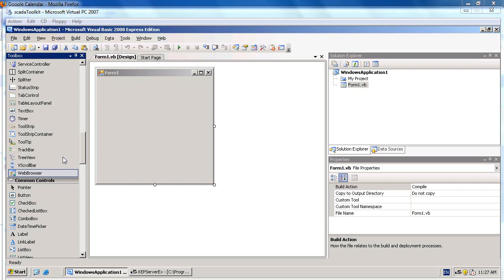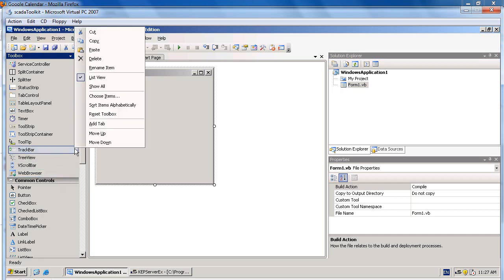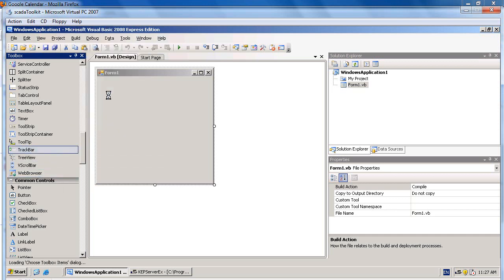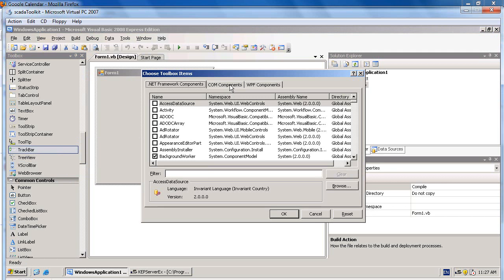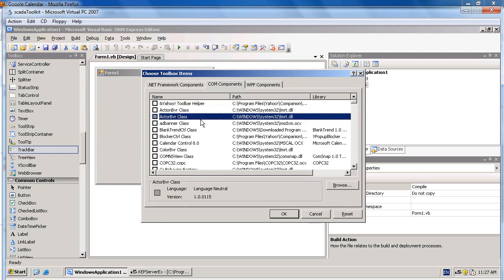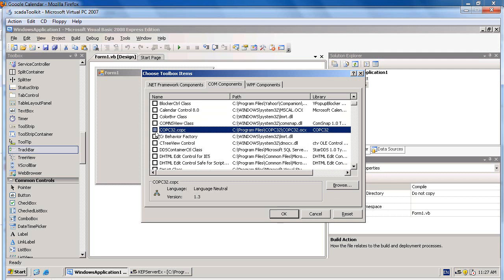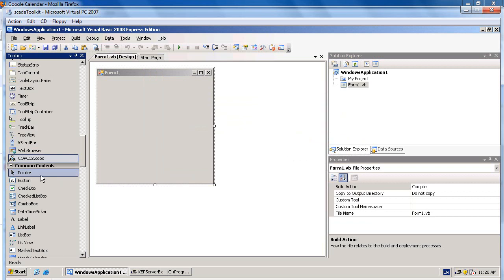First of all, we need to add the COPC control into the toolbox by right-clicking on the toolbox and choosing items. In the COM Components tab, after you have installed COPC32, it will appear in the list. Check on COPC32.COPC and click OK.